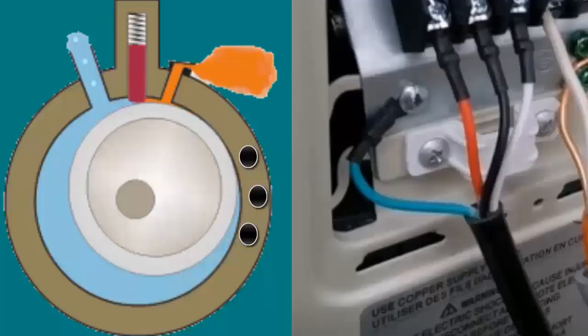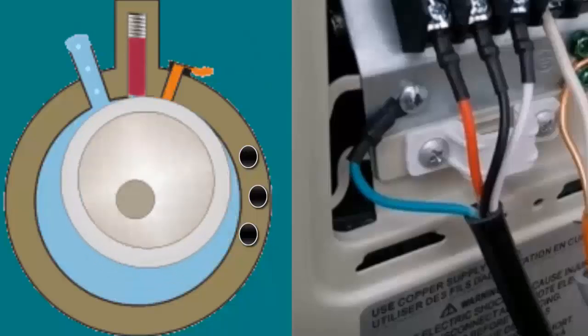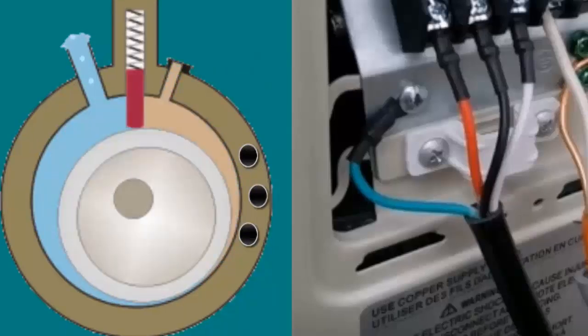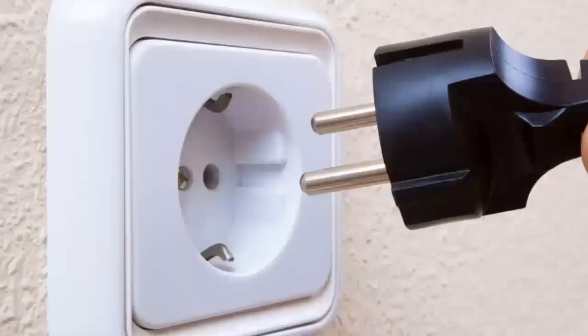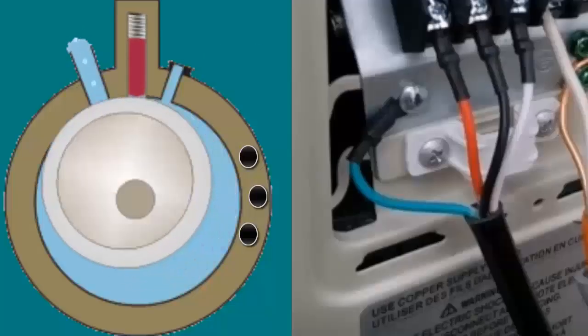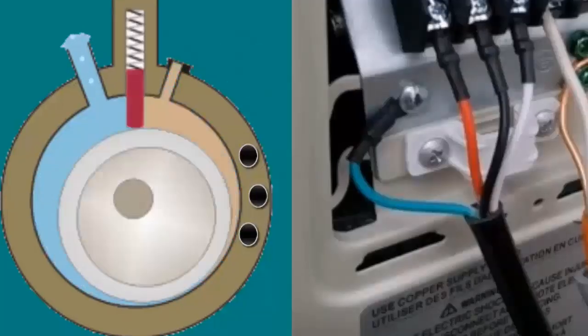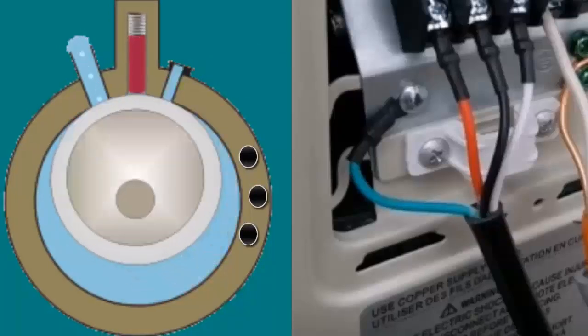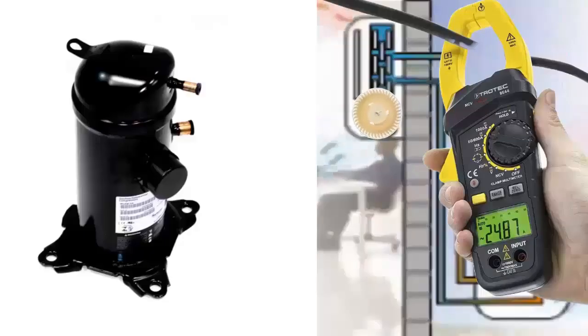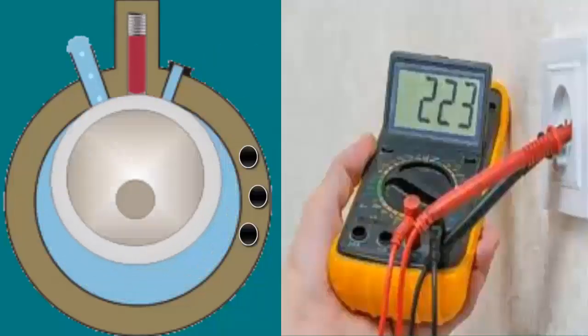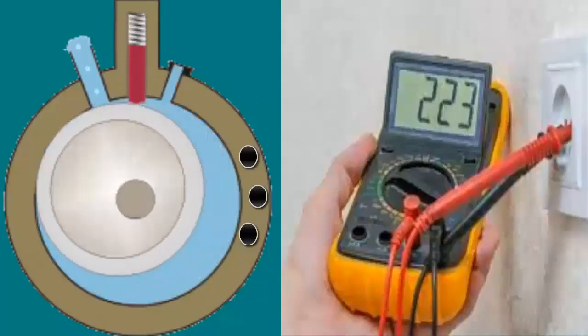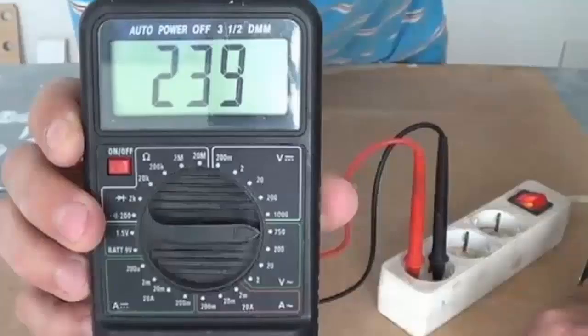To resolve the above issues, the following steps are recommended. 1. Disconnect the equipment from the electricity for several minutes, turn it back on, and check if the error reappears. 2. Check the connections and cable quality in the compressor and the external electronic board. 3. With a multimeter set to the AC voltage scale, check the correct voltage from the external power supply.